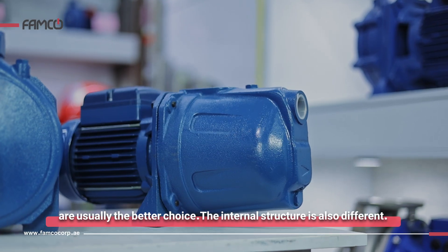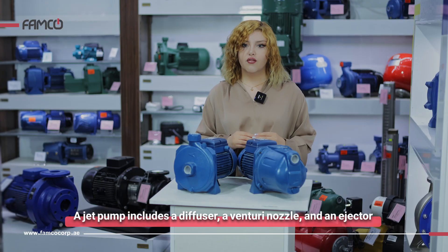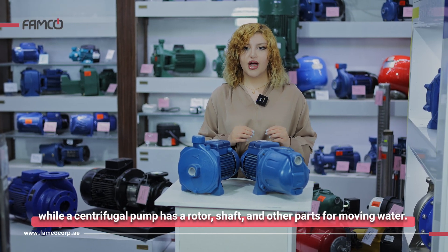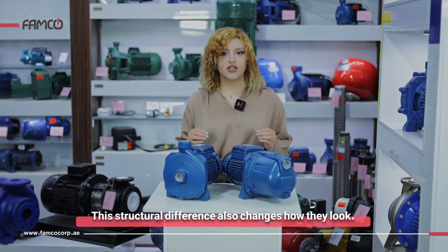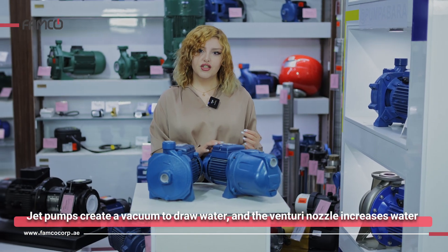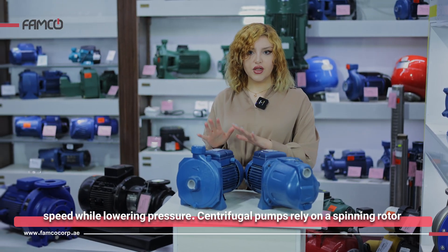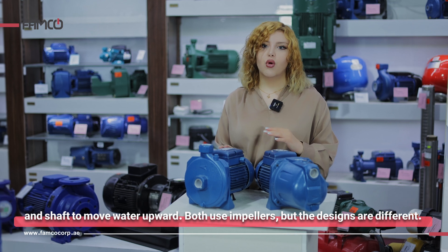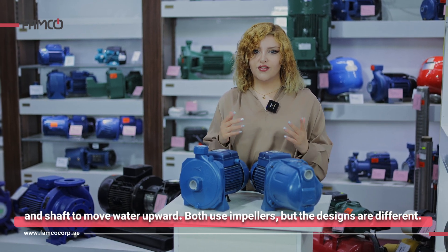The internal structure is also different. A jet pump includes a diffuser, venturi nozzle, and ejector, while a centrifugal pump has a rotor, shaft, and other parts for moving water. Jet pumps create a vacuum to draw water, and the venturi nozzle increases water speed while lowering pressure. Centrifugal pumps rely on a spinning rotor and shaft to move water upward.